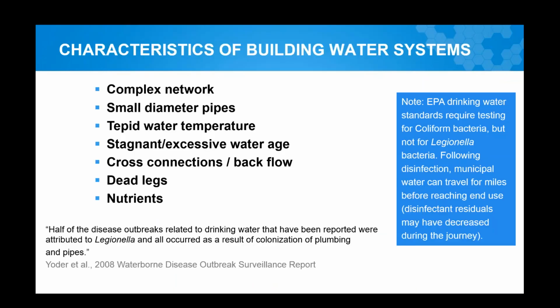What are some of the characteristics of a building water system which cause amplification of Legionella? Having a complex network of piping. This leads to dead legs and stagnation. Small diameter piping, so there's more area of the piping covered with a biofilm. Tepid water temperatures are right in that area where Legionella amplify. Again, stagnant and excessive water age.